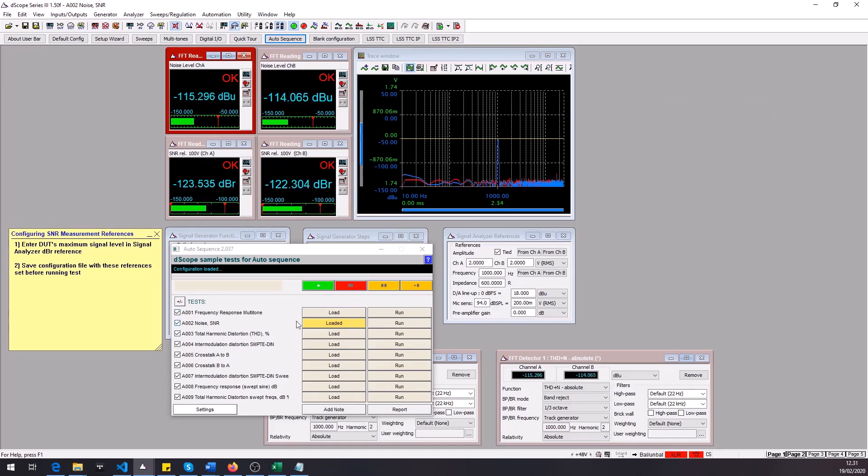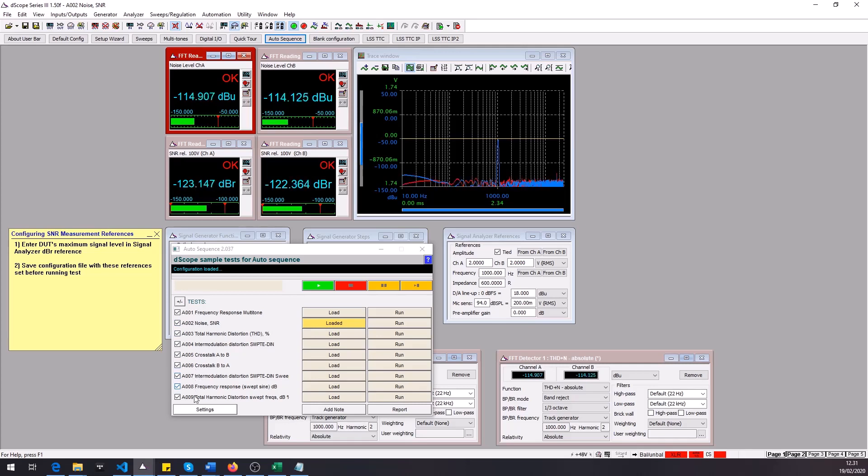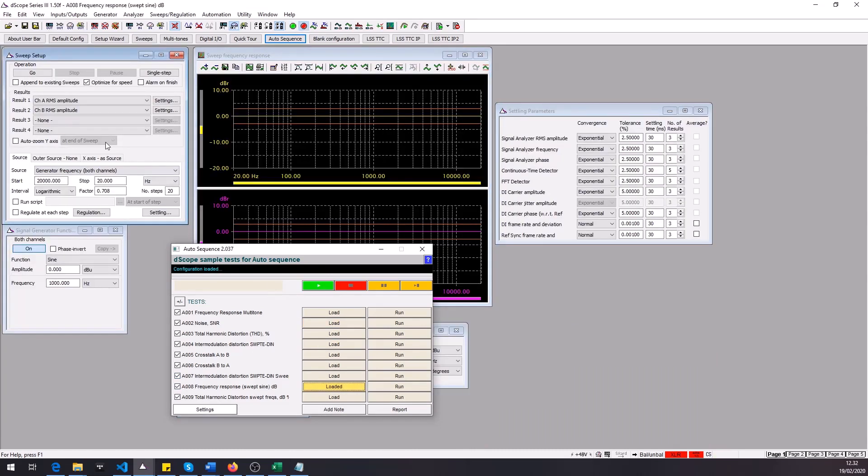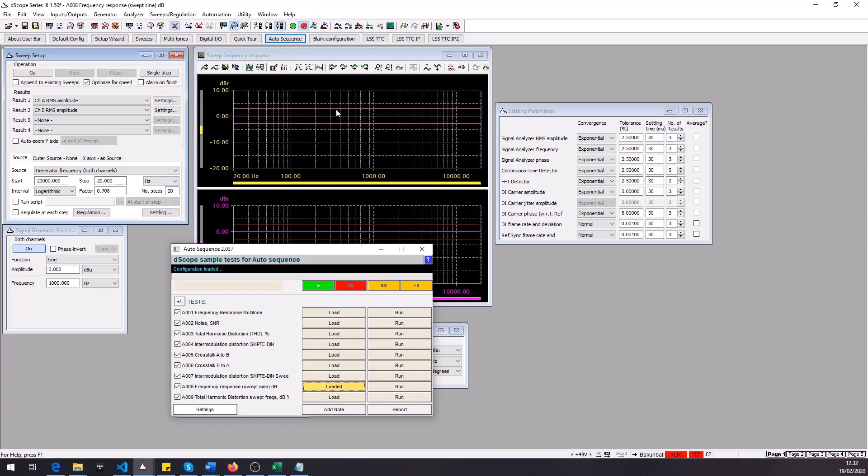So this is how the tests number two to six are set up and then tests seven to nine are sweeps. For example the test number eight is a frequency response sweep and here I've set up the amplitude running against a range of frequencies and then I also have the limit lines set up here so that the AutoSequence tool can check if the frequency response stays within these limit lines.